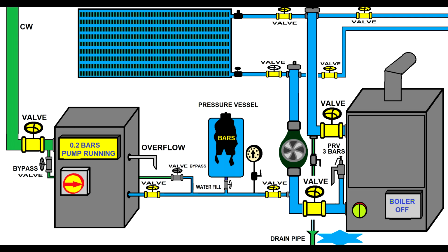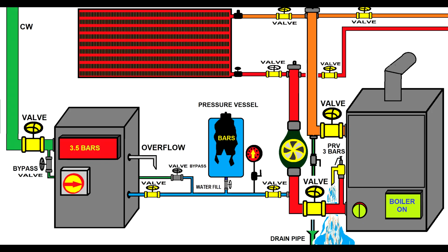The problem is that on the second day when you reheat the heating agent, you will again lose a quantity of heating agent until the pressure stabilizes just below or equal to 3 bars. So this is a bad thing, and this is why you should be very careful when you design an installation and calculate its volume. So please pay attention to this situation.